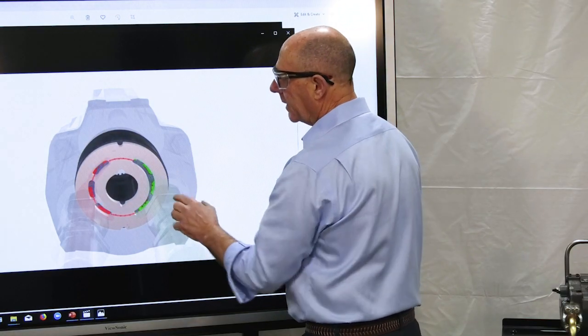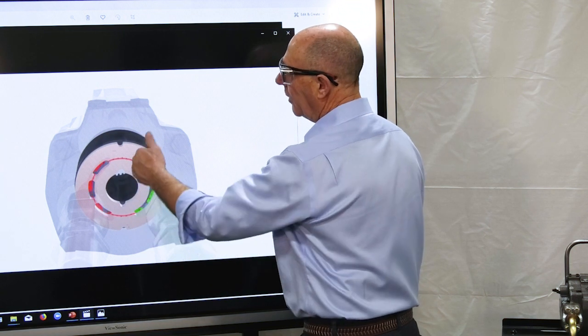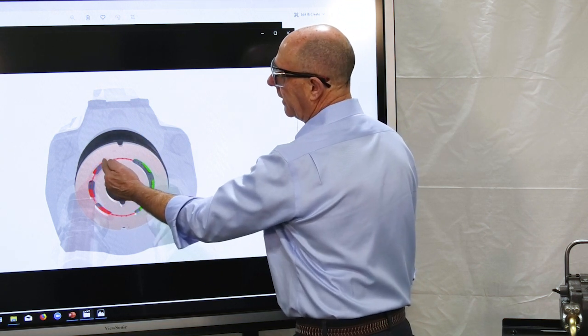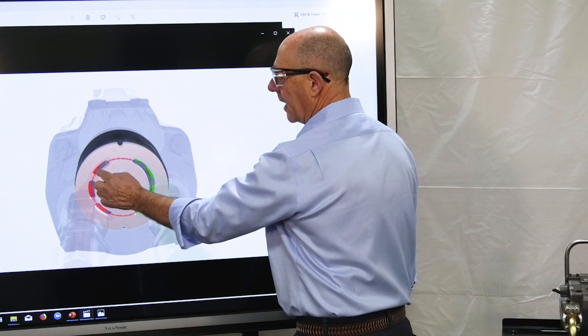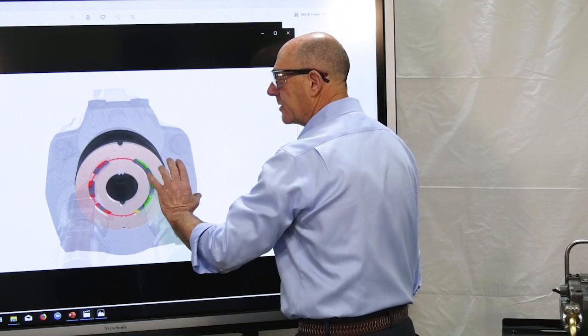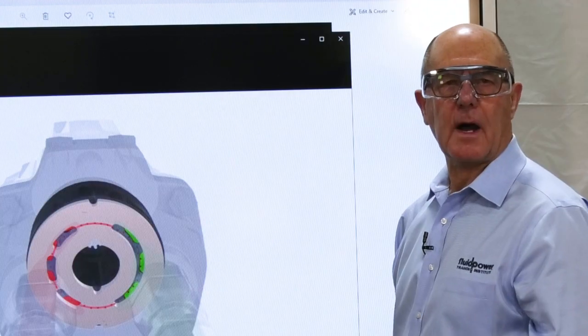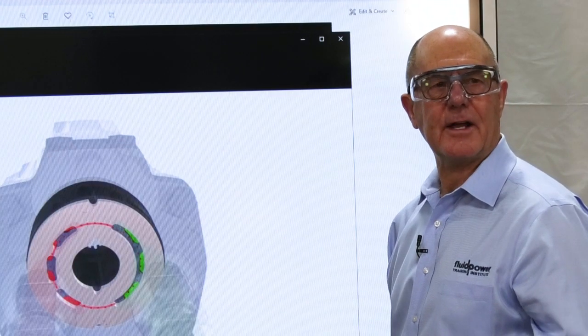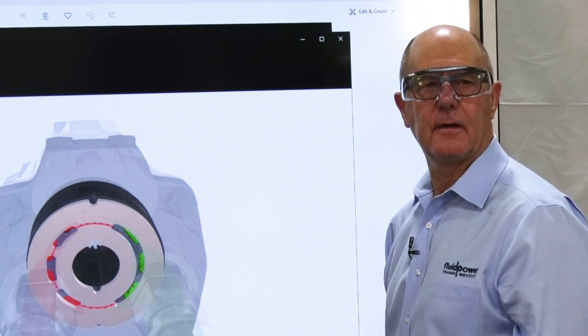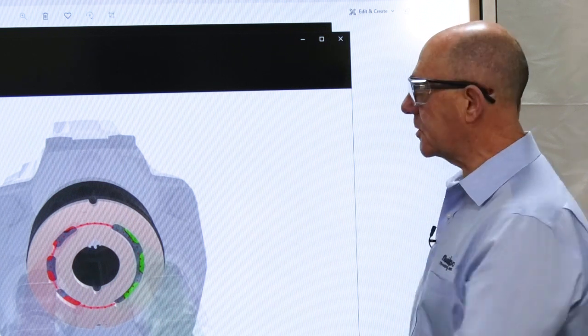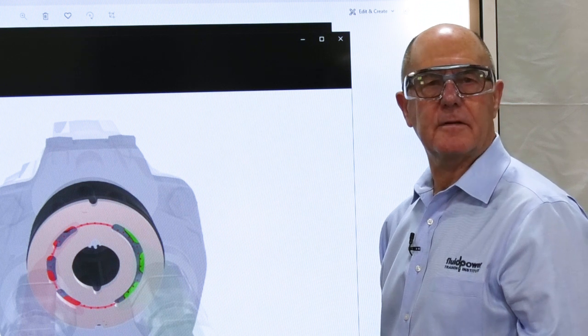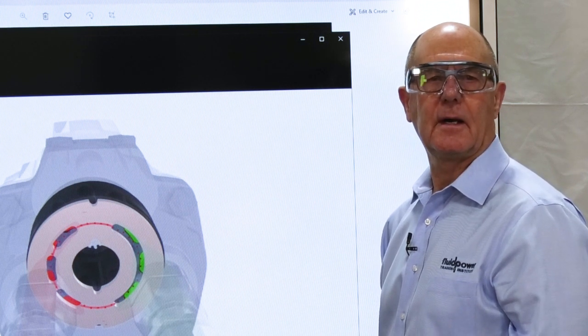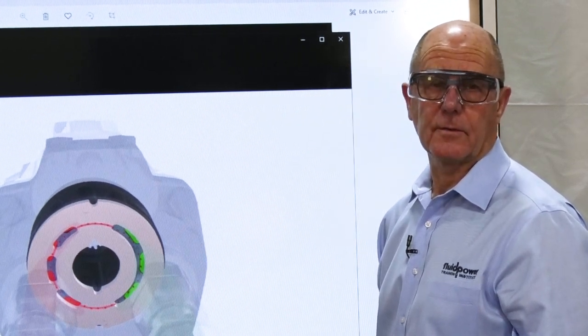Contrary to popular belief, that oil cannot get into the housing. The only oil that will get into the housing is oil that leaks across the plate or into the center of the plate. Any oil leaking from the high pressure side of the pump to the intake is not going to find its way into the case. During my research I found that unless the pump had suffered a catastrophic failure, in very few instances did the contamination breach the space between the elongated ports and the case. Since my discovery would scientifically invalidate case flow testing, I decided to conduct a test to prove my findings were scientific.